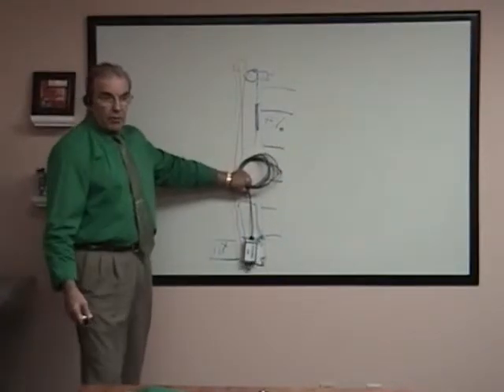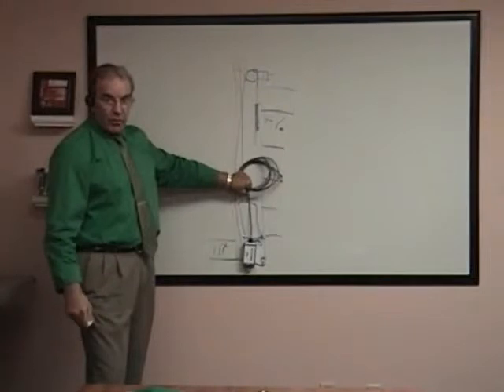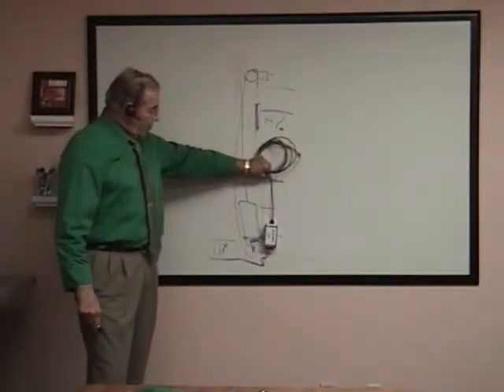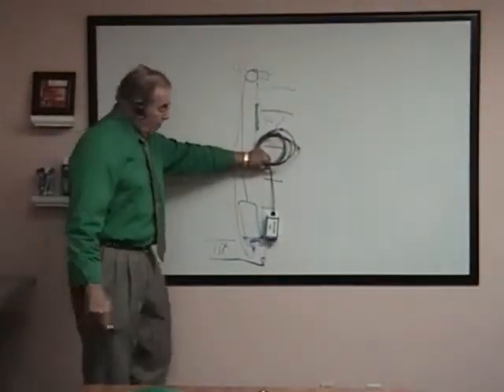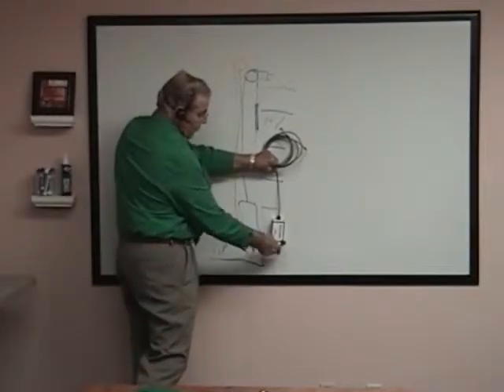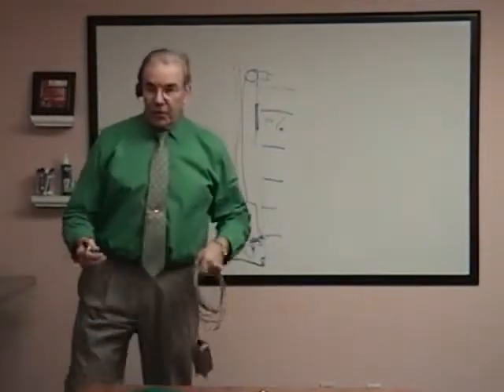Or if you have a pit that usually has a little liquid in it, maybe you want to put it 2 or 3 inches off the bottom. So that'll allow 3 inches of liquid before the switch trips. That's up to the installer. That's his job.